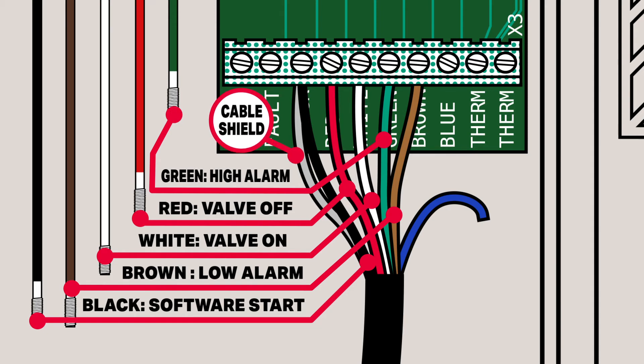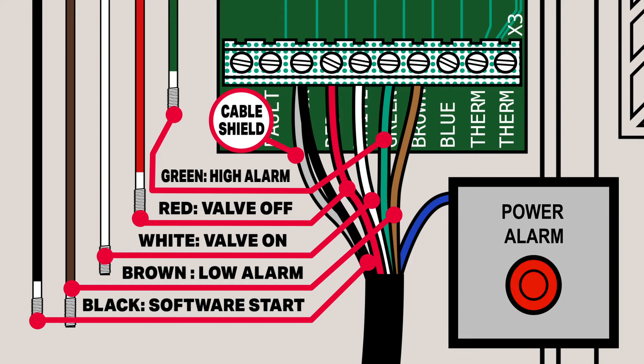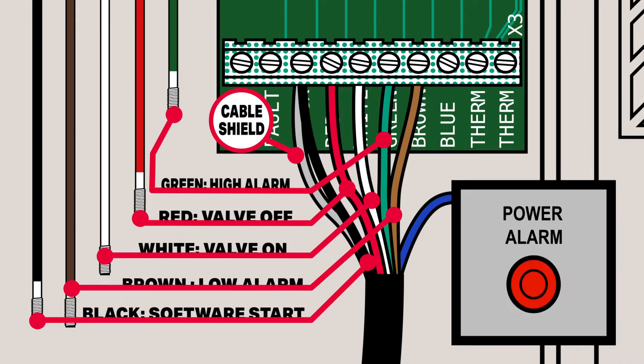The bare wire cable shield connects in with the black sensor wire. The power LED on the panel will flash red and green and not allow the controls to function if the wires are not connected properly.